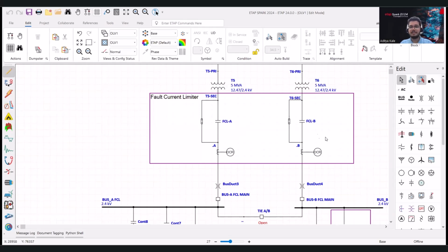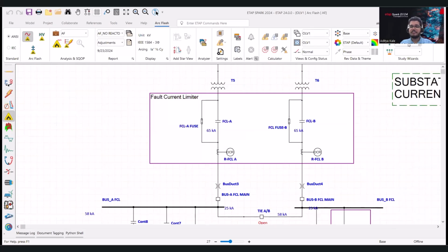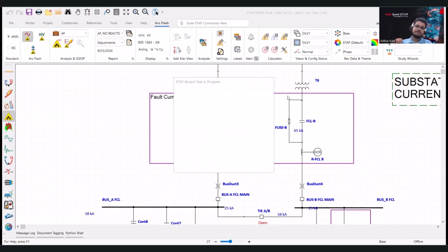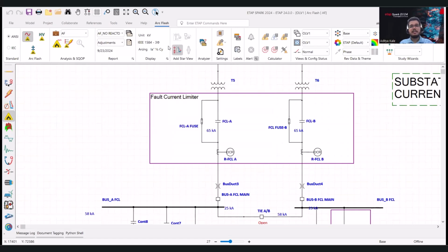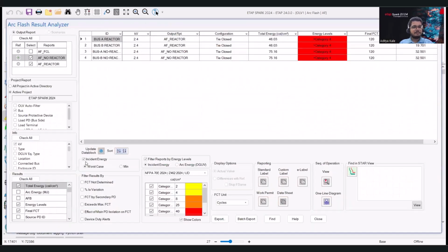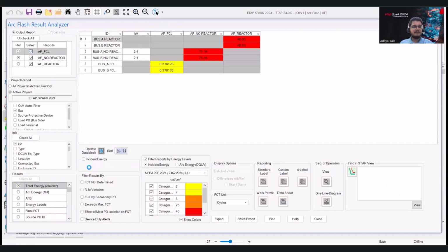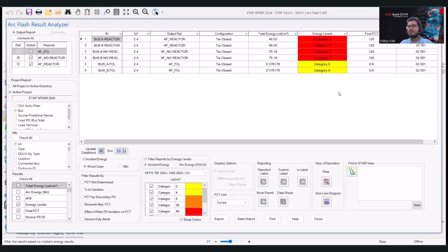So let's look at the fault current limiter in action. We can run the arc flash study. There we go, that was pretty quick. Let's look at the analyzer results that we have. So let me add in the FCL. Boom, right off the bat, we see it. The results are considerably good.